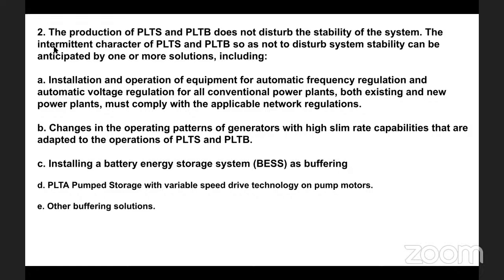The intermittent character of PLTS and PLTB, so as not to disturb system stability, can be anticipated by one or more solutions, including: A, installation and operation of equipment for automatic frequency regulation and automatic voltage regulation for all conventional power plants. Both existing and new power plants must comply with the applicable network regulation.